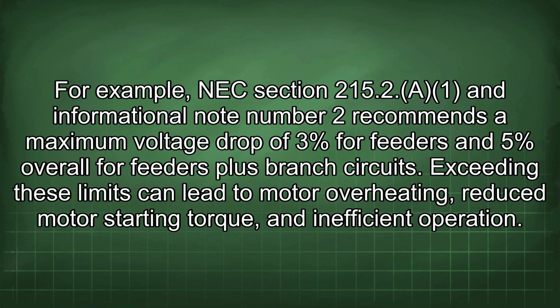For example, NEC Section 215.2(A), informational note number 2, recommends a maximum voltage drop of 3% for feeders and 5% overall for feeders plus branch circuits. Exceeding these limits can lead to motor overheating, reduced motor starting torque, and inefficient operation.